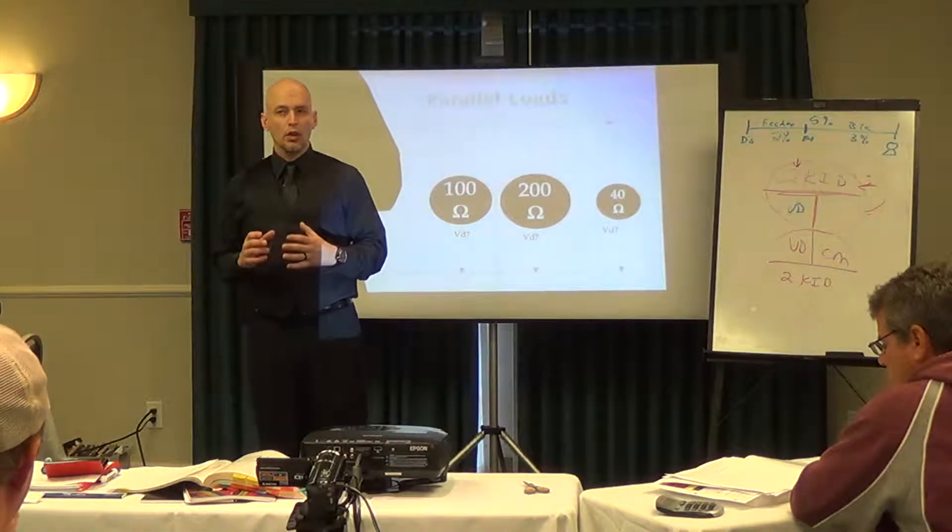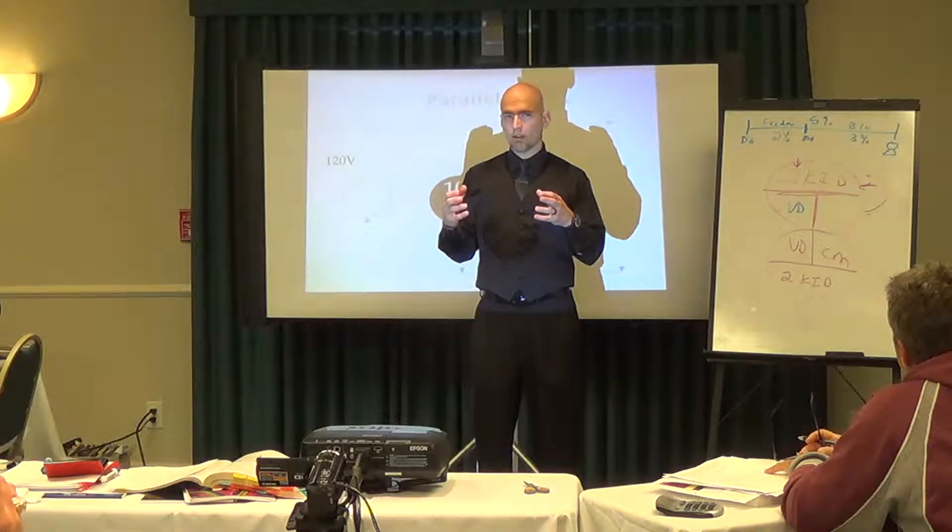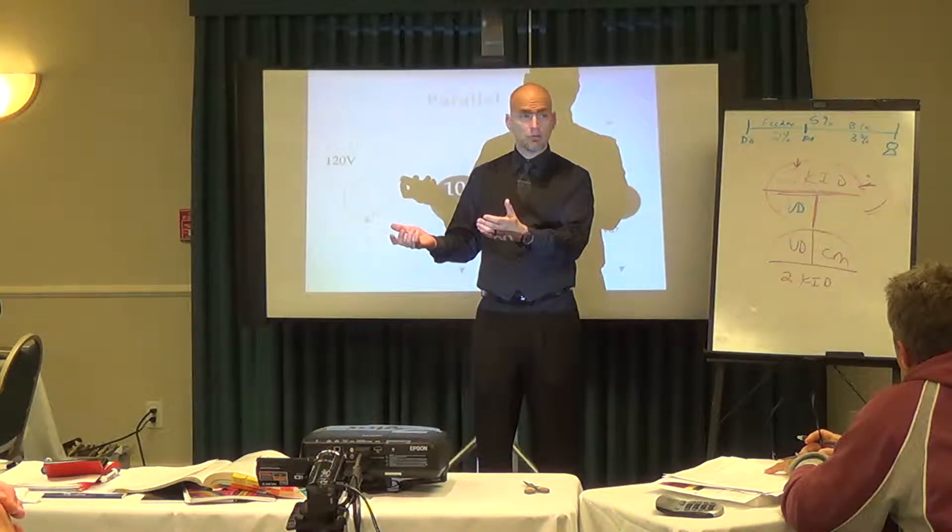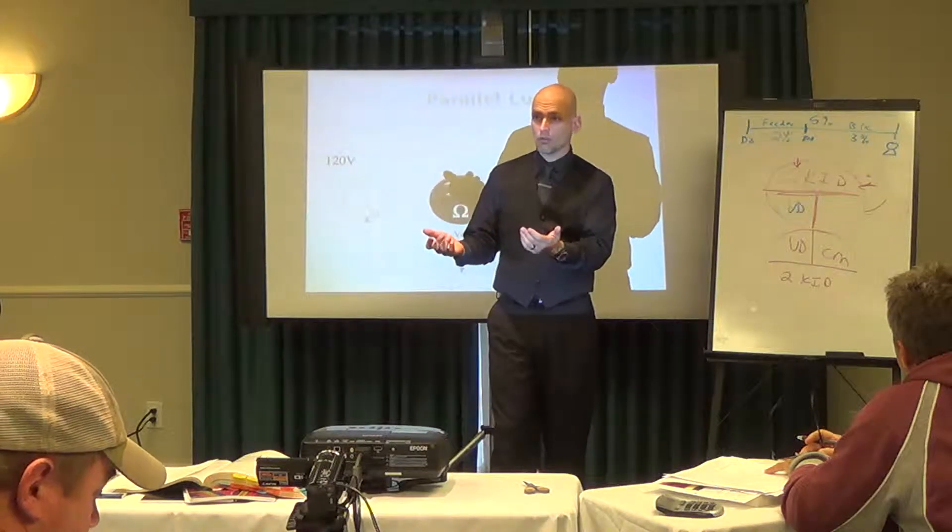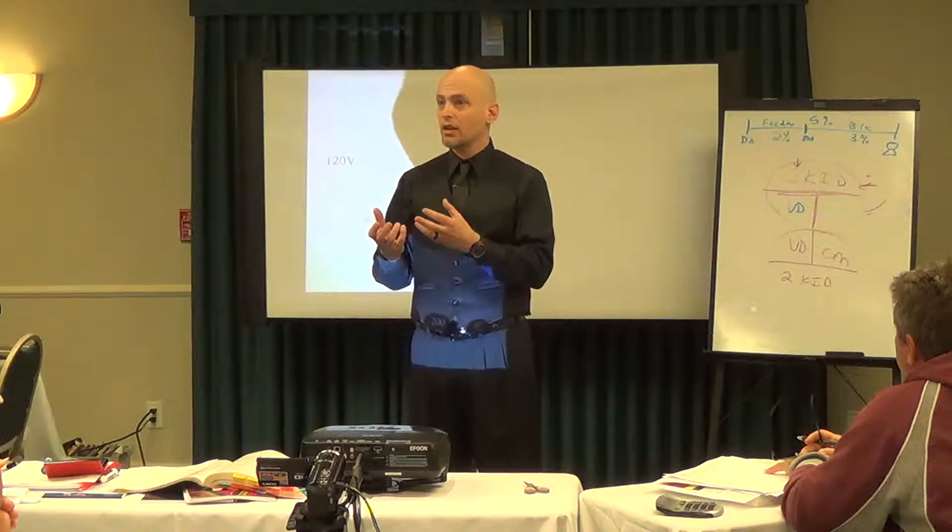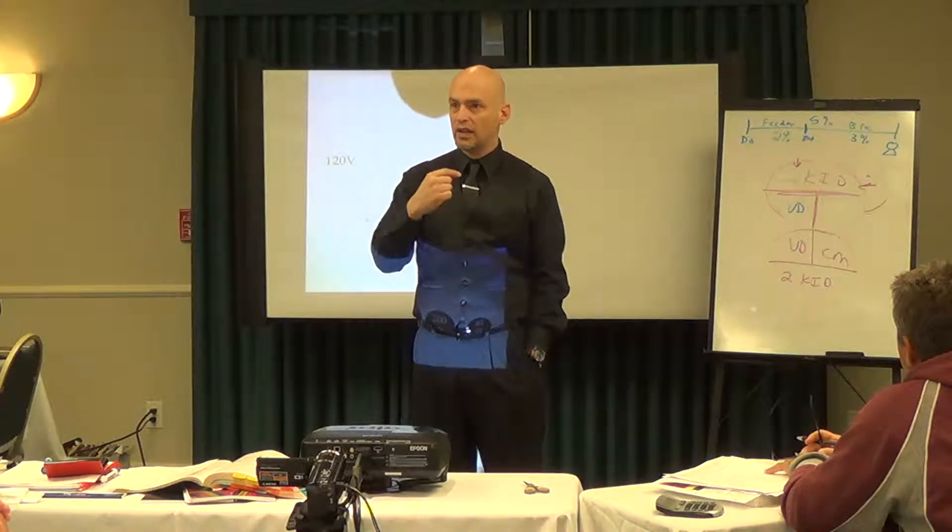Absolutely, and that's probably the most common mistake a lot of guys try to do. We're talking about voltage drop in terms of percentages, but it's a percentage of whatever the system voltage is, so that's going to be a number that will change based on whether it's a 120 volt circuit or 240 or 208. Those numbers of system voltage is really, representatively, that 3% is just what we don't want to lose out of that, which is that number of volts that this thing gives us.